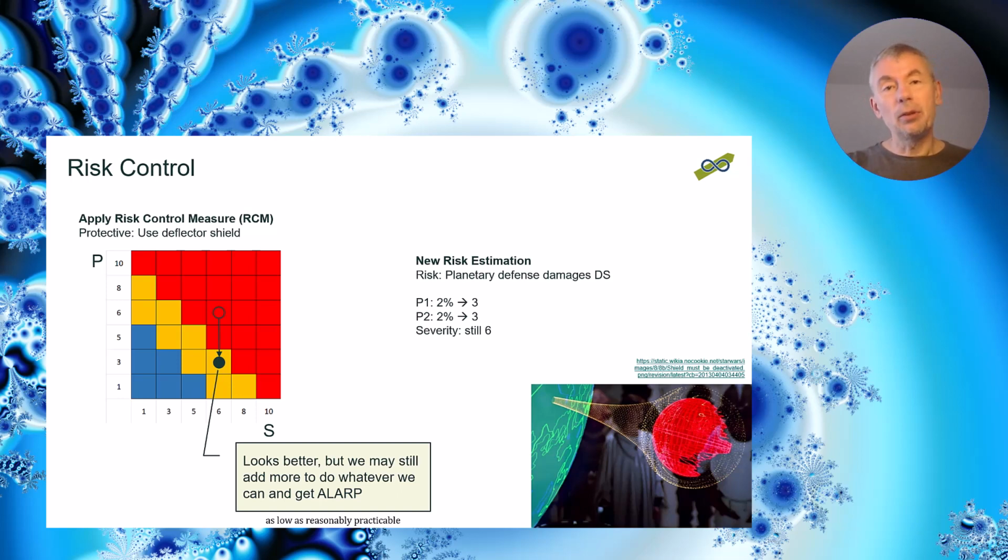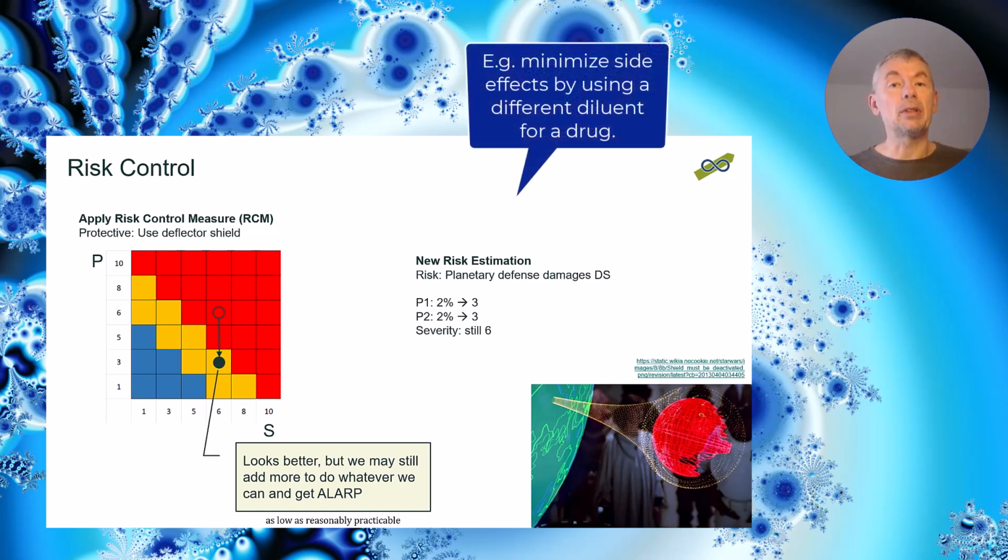And you also see, if you follow the track of how this risk evaluation moves through these quadrants, that the severity is usually not affected by risk control measures. You work with the probabilities. There may be some cases, but if you look at the risk, if you explode, that's always exploding. It's just how you manage the chances that you're not exploding, you're affecting with risk control measures. But there may be some other medical devices where you can also influence the severity.